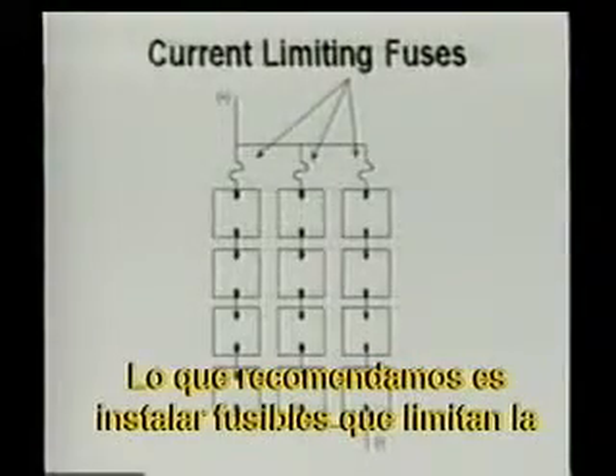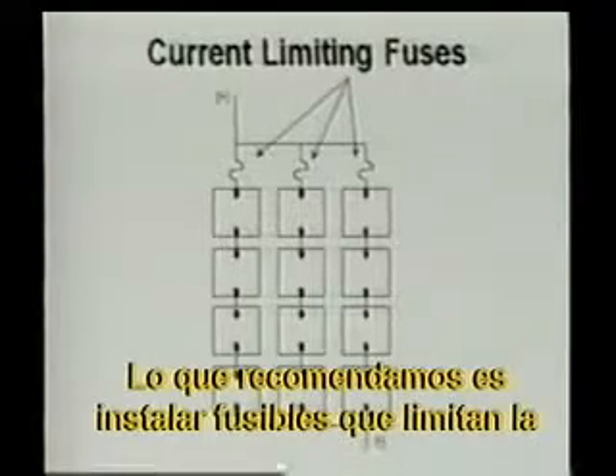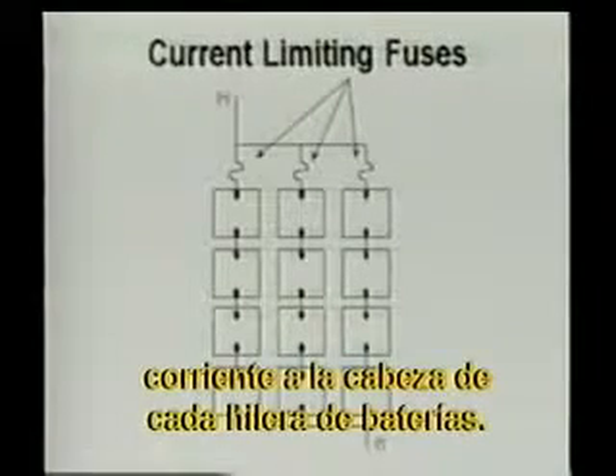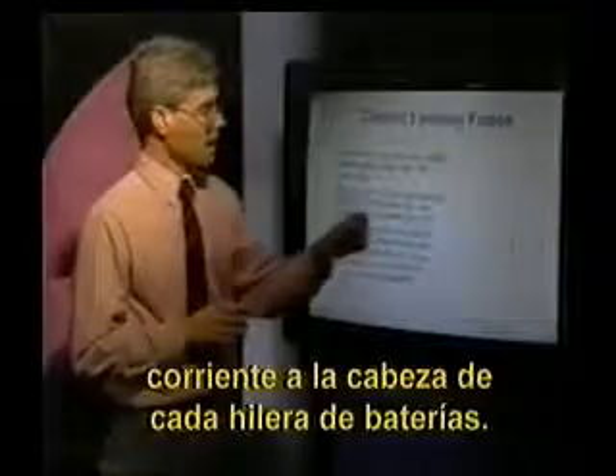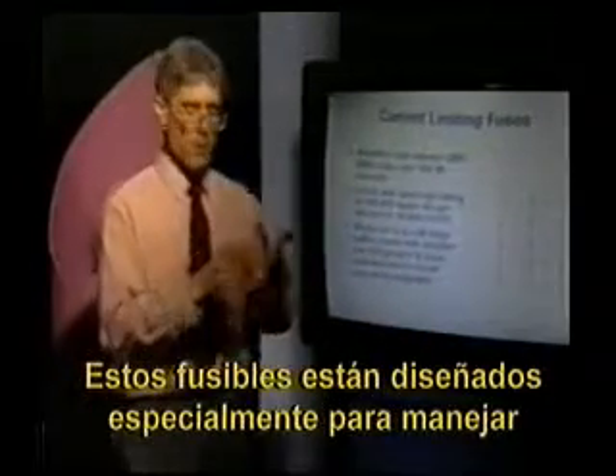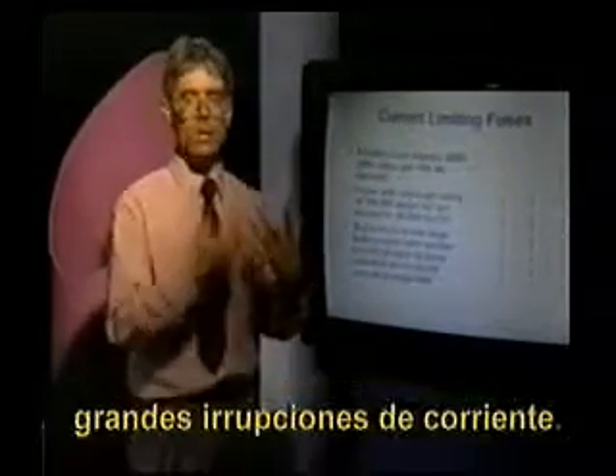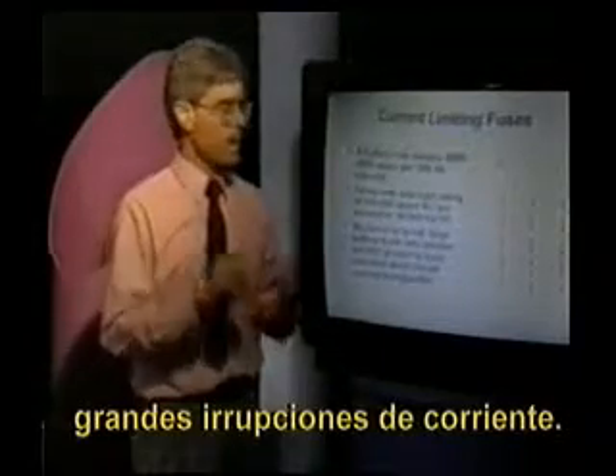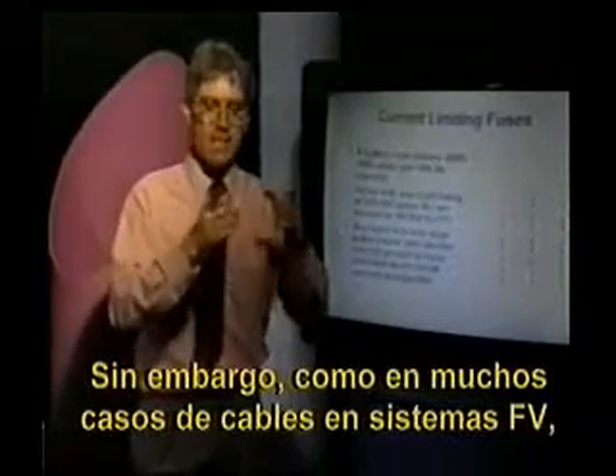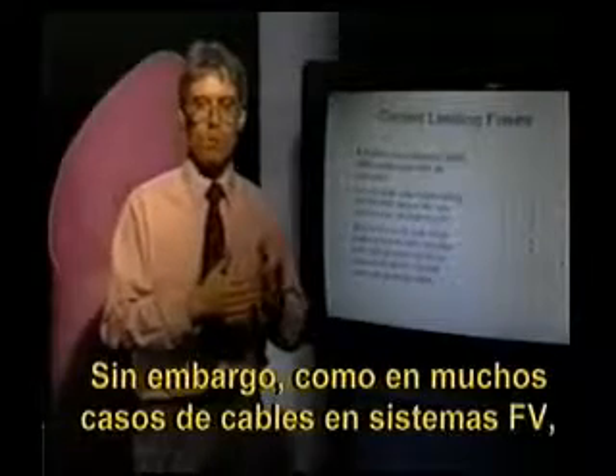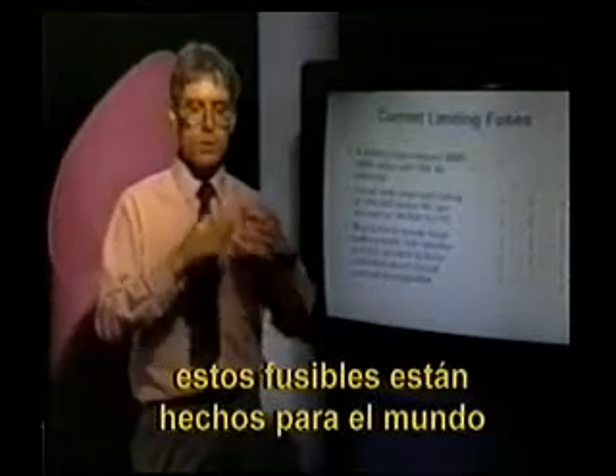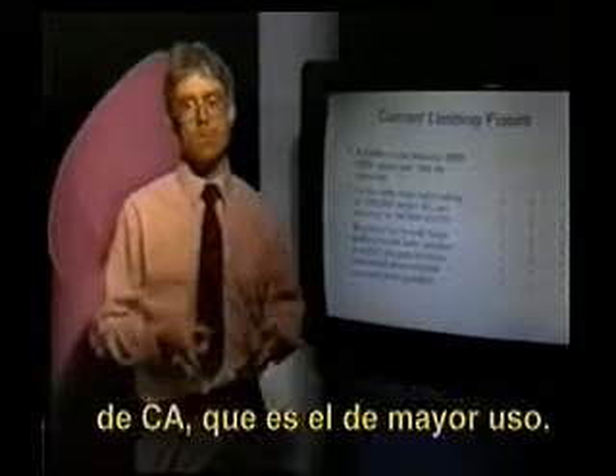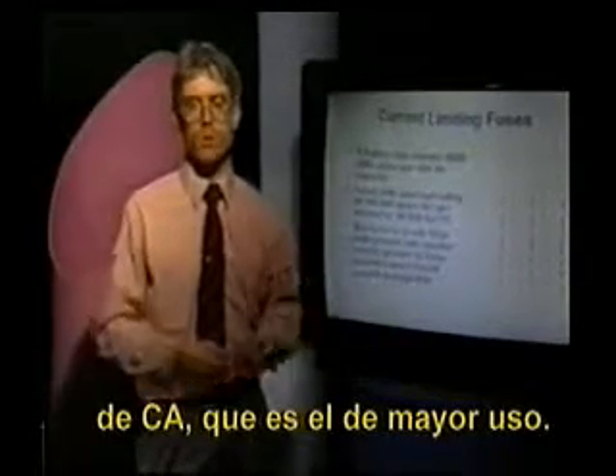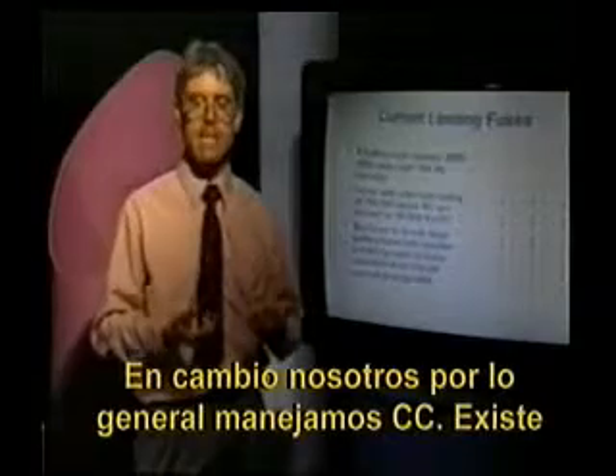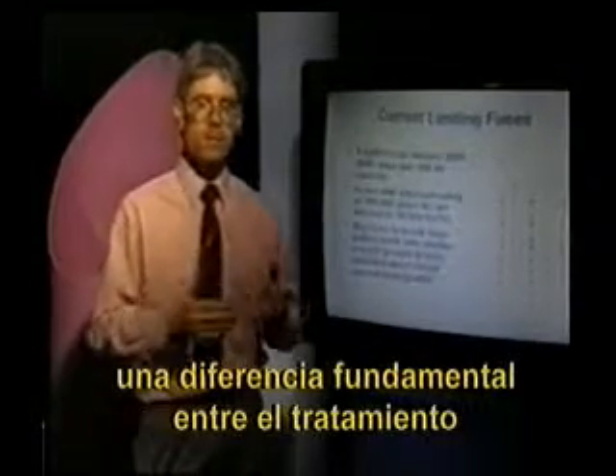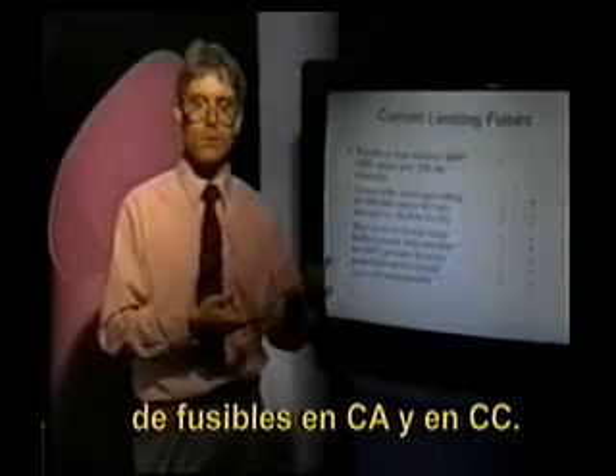What we recommend is to install current limiting fuses at the head of each one of our battery strings. These current limiting fuses are specially designed to handle large inrushes of current. However, as in many, many cases when we look at wiring in photovoltaic systems, these fuses are rated and typically designed for the AC world. That's the majority of their usage around the world. We're typically dealing with DC. There's a fundamental difference between AC current treatment of fuses and DC.